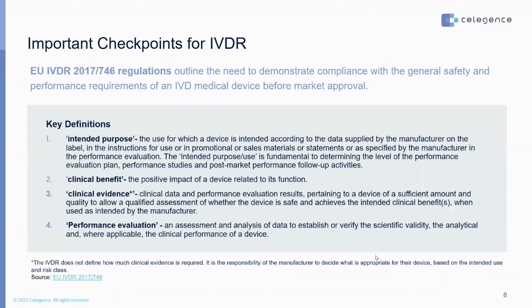So, in order to have a complete performance evaluation, it's important to understand what the intended purpose of the device is, what the clinical benefit is, and what exactly is meant by clinical evidence under IVDR, because the requirements for clinical evidence under IVDR are different from what is required under the MDR. So for the intended purpose, the definition is quite simple. It's the use for which a device is intended according to the data supplied by the manufacturer. And this data is either on the label or the instructions for use or any promotional materials that accompany the device.